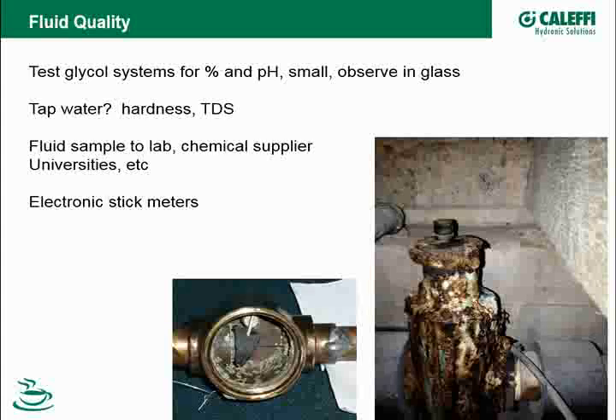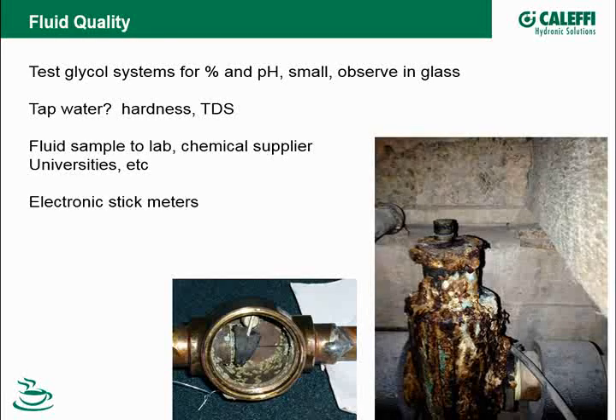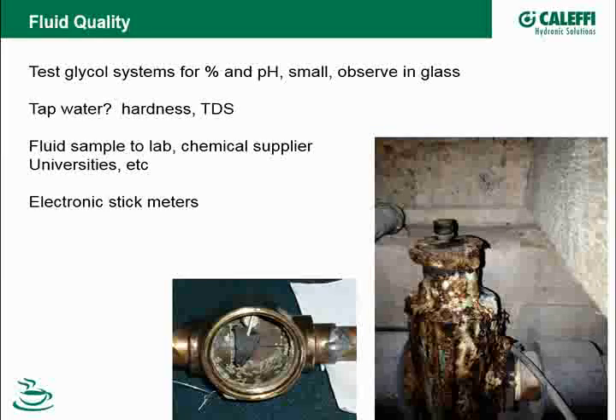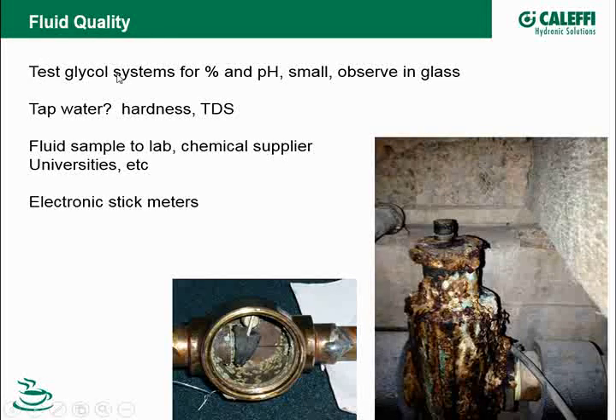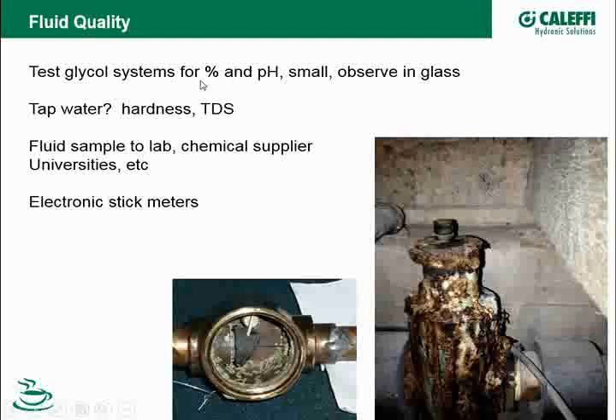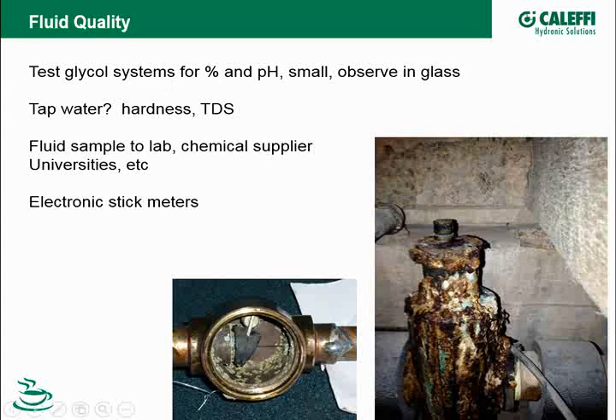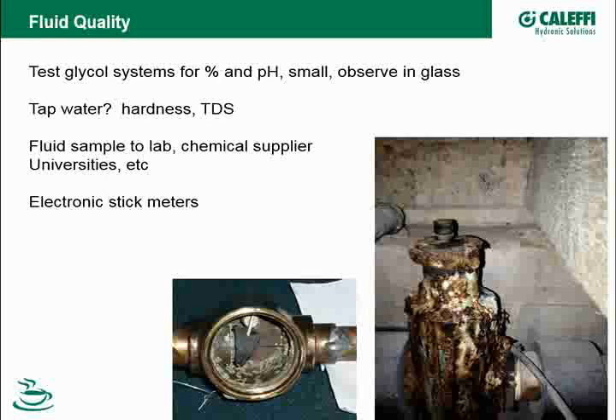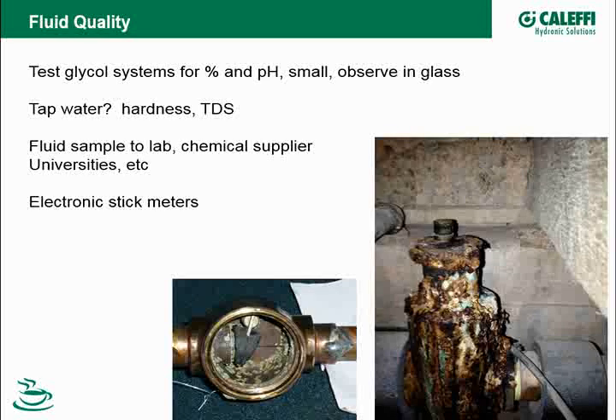If you've got panel radiators or something out there that are getting some kind of buildup of scale on them, they're not going to give off the heat that they would if they were a clean surface. So you want to test it. Now, glycol systems, there's a couple different tests that you want to do with that. You want to make sure that the glycol percentage, the freeze percentage, is right, so you don't have problems with cold weather and the power going out and freezing something. So you want to use something like a refractometer for that. You can just put a little drop of it on there, look down through it, and see what the freeze protection is.